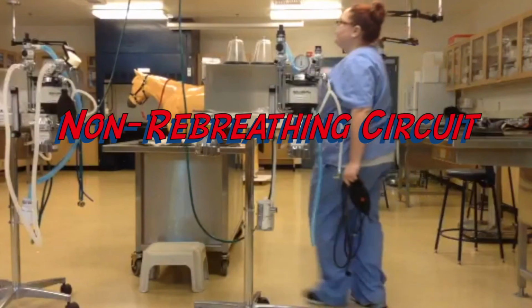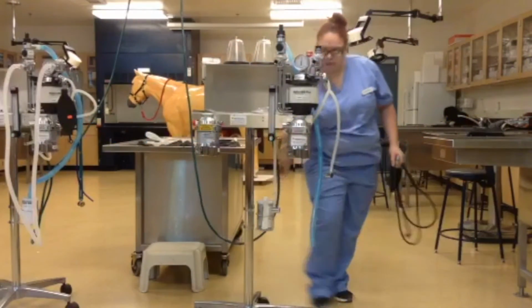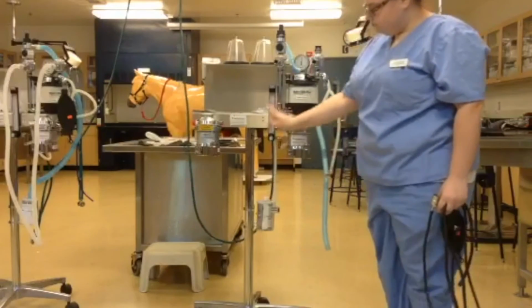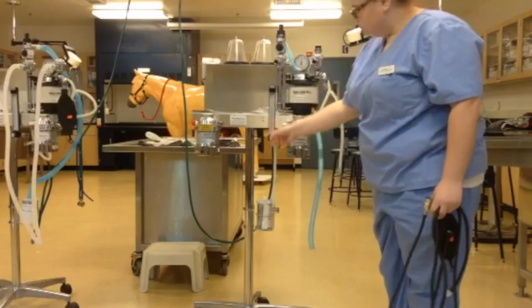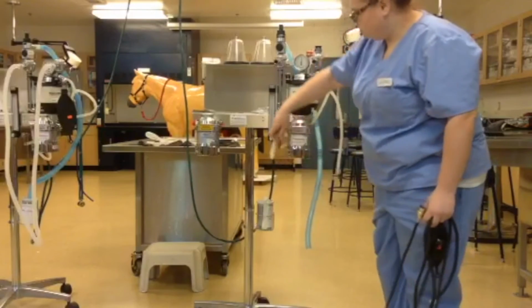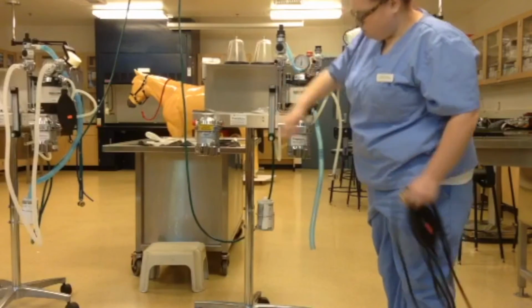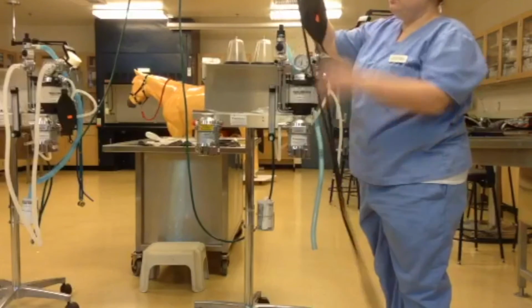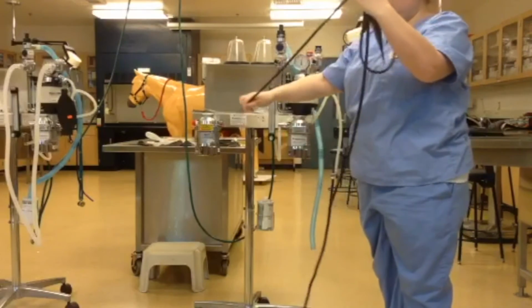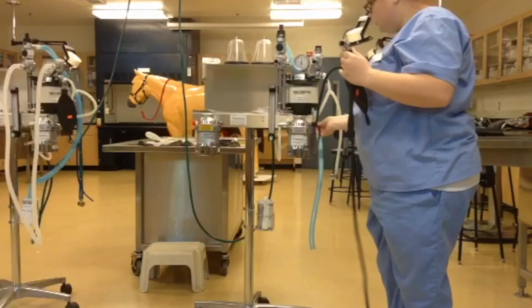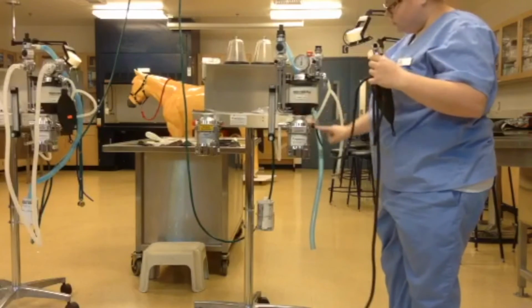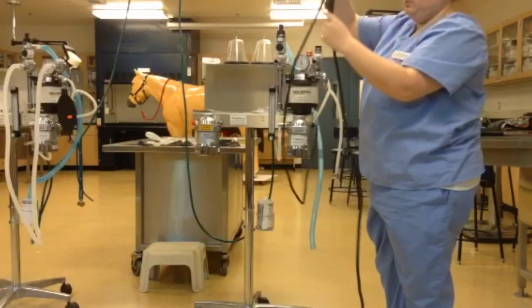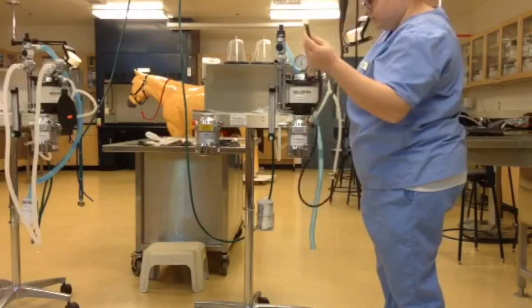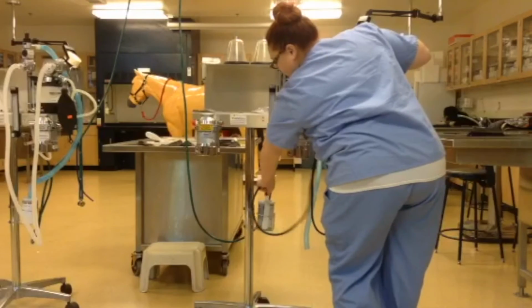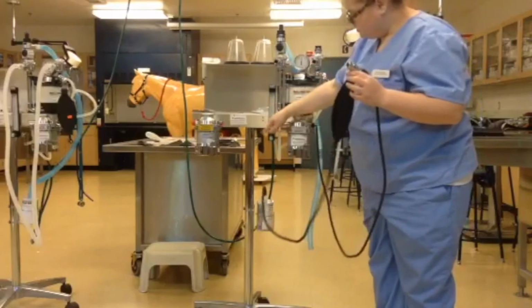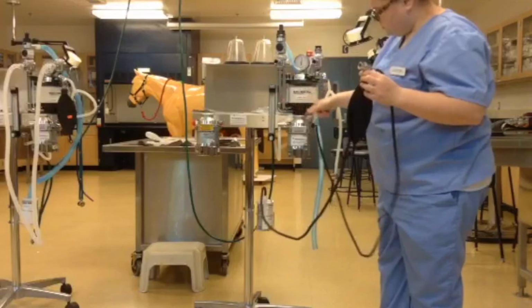Now I'm checking the non-rebreathing circuit. Checking that the oxygen is connected to the flow meter. We have our flow meter. Then I'm making sure that we connect to the inlet port of the vaporizer. Then I'm going to connect our non-rebreathing system to the outlet port, so that we have oxygen and anesthetics flowing through the connector, which will flow through the reservoir bag and then connects to the scavenging system, which contains carbon dioxide, anesthetics, and oxygen.